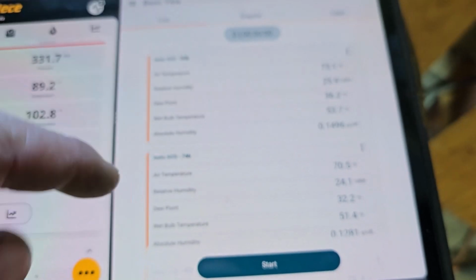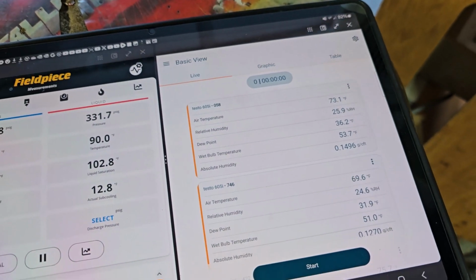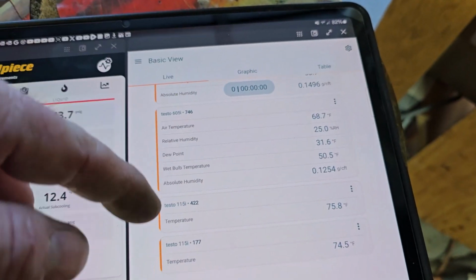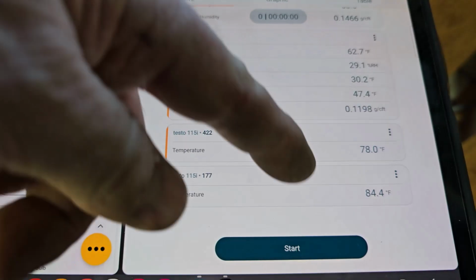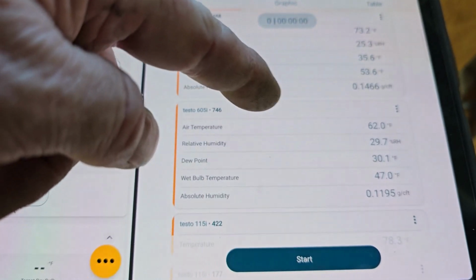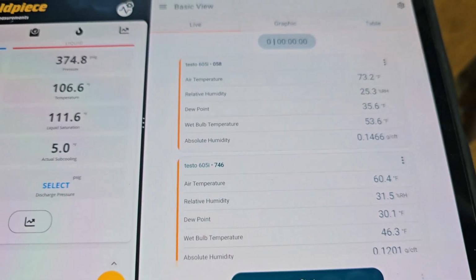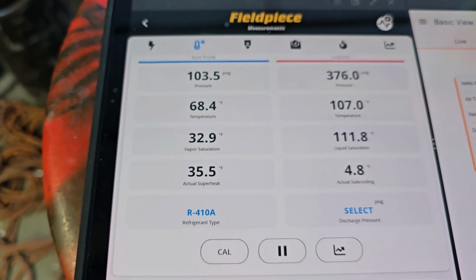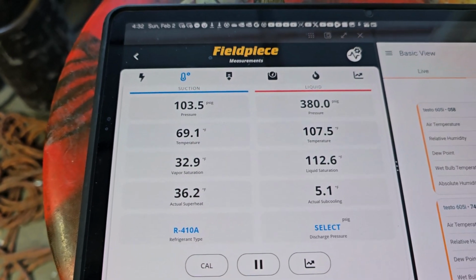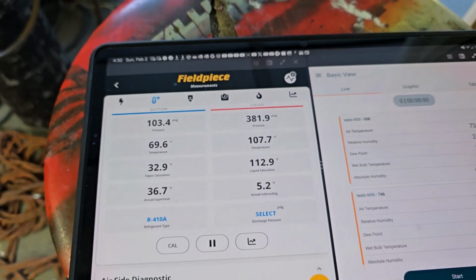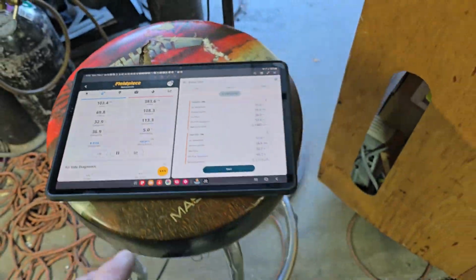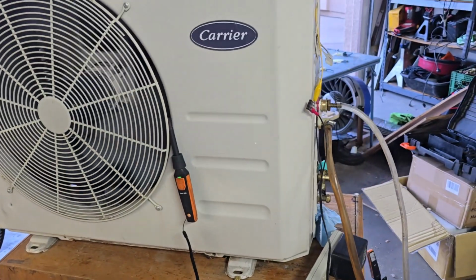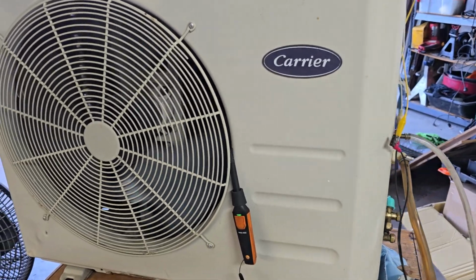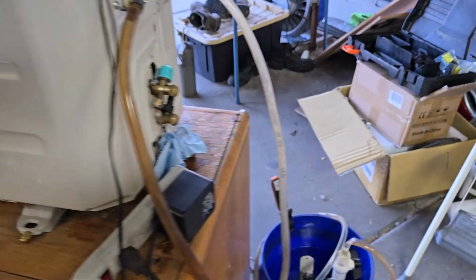So there's some pressures. You can see this temperature drop. Earlier I had almost a 20-degree split when I was adding some refrigerant. And there's my water temperature. So that's entering water, and that's leaving. And my entering and leaving air. And then my pressures are over here. It's not going to be exact on the pressure. I figure it's close enough until I actually do mount the unit. I just want to make sure this thing works good before I do that. And let's make sure it's flowing enough.